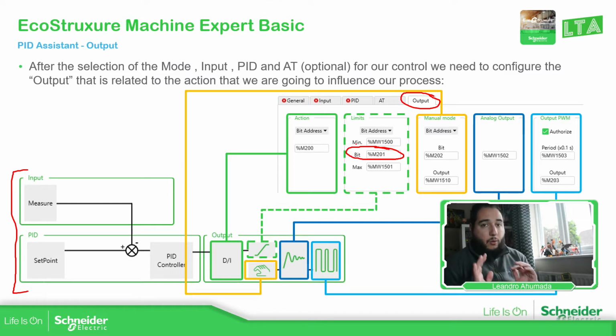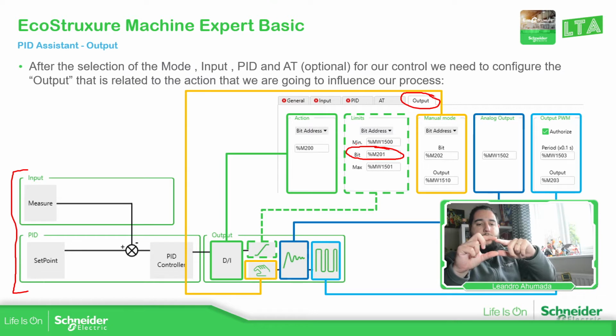It's not the same as the conversion that we have in the input, where you have the input and then you have the conversion, and you can specify the signal to go to this size. Here on the output, even if you generate a signal like this, and you compare the size, if you use the limitation, the signal just goes up to here and stays there. It's just a limit of the value. It's not the conversion, so you need to be careful here.